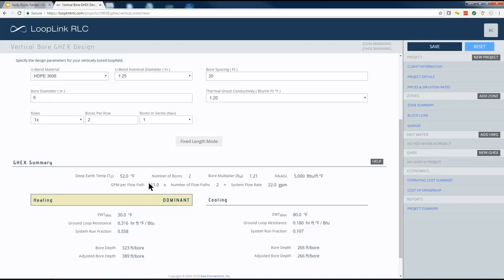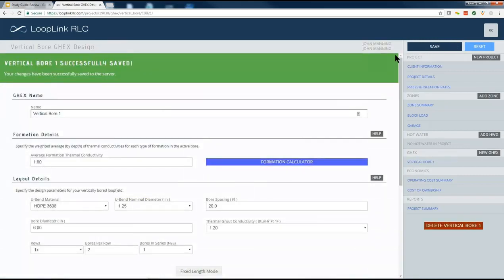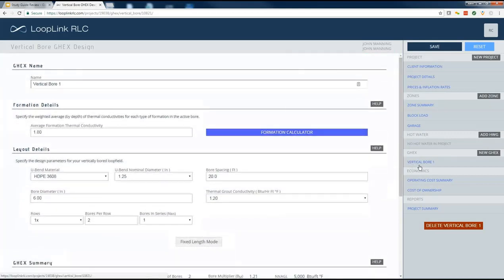Even though the flow, GPM per flow path, is a little bit higher, I'll take a look at my pumping power calcs, but this is probably the design that I would run with personally. 2 bores to 400 feet with that 1.2 grout would serve this entire system. So let's go ahead and save that. And now you can see we've got a vertical bore design that's been saved and applied to the project.